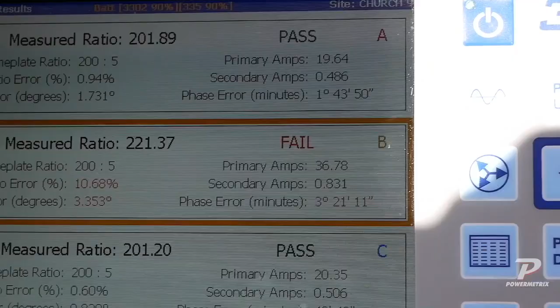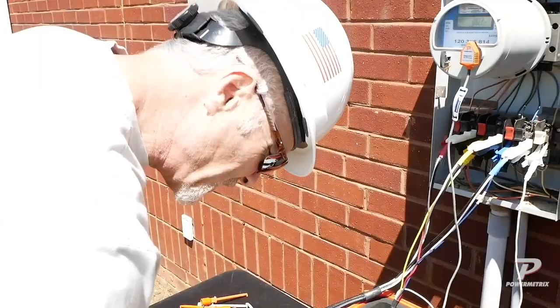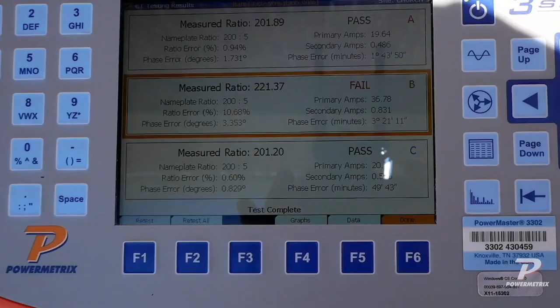So we got a fail on that, and we're still consistently at 10% of a ratio on B phase, Jonathan. And it's also giving me a phase angle error on B phase. So we'll go back over here and take a look at the B phase.